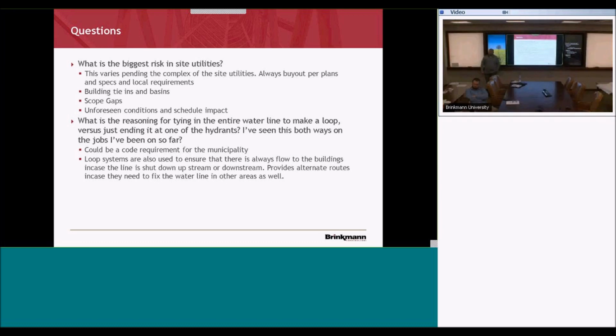So does that cause a big leak? No, it didn't. I mean, it held, but we just had to go replace the blown regulators, and then we had to bring it down to 2 PSI in the basement for the whole building.